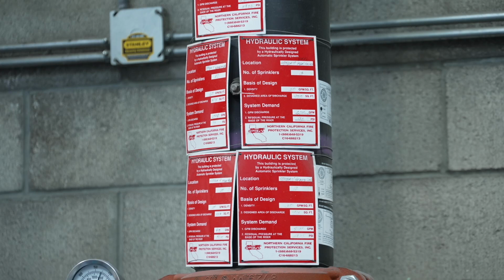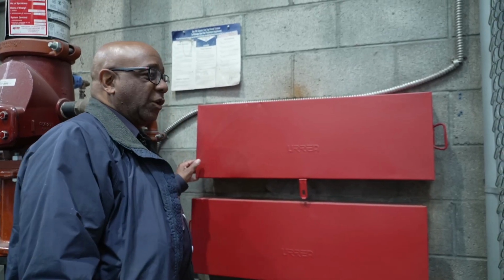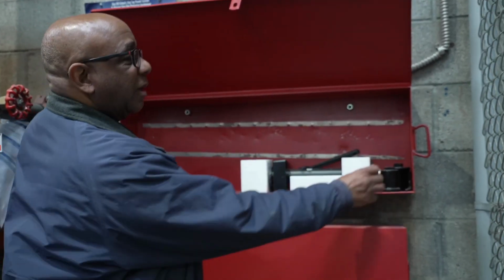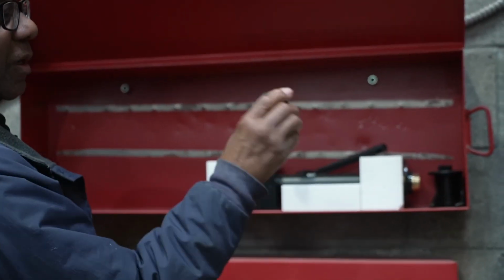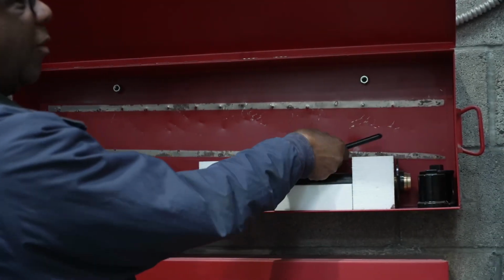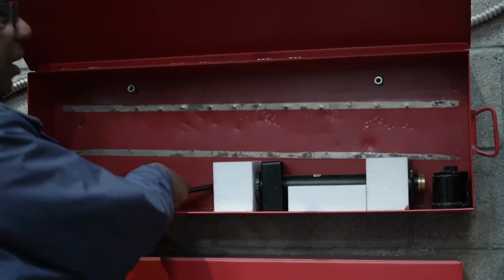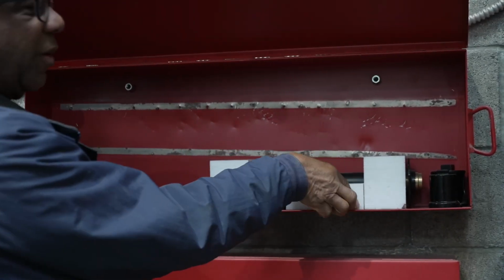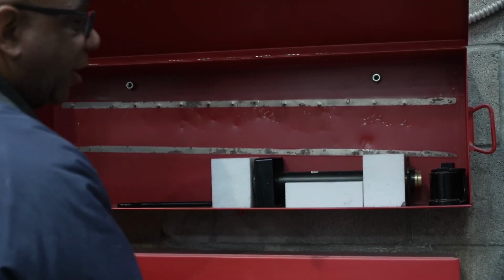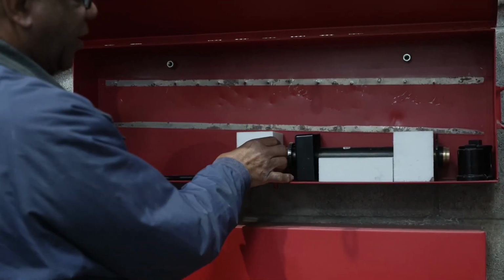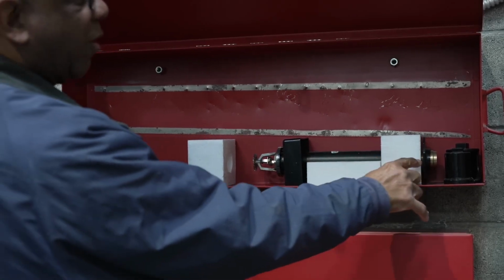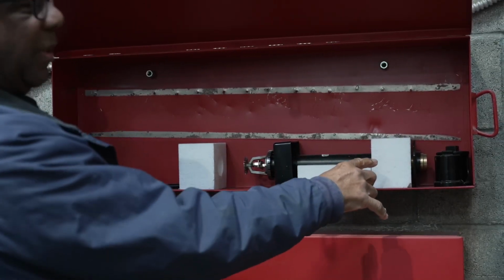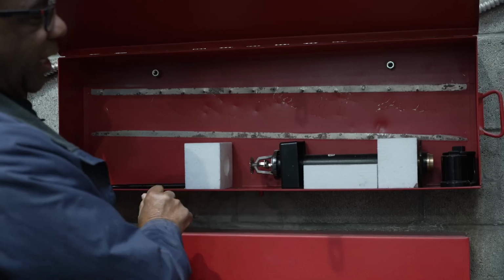So when you have refrigerated or freezer occupancies, there's going to be a specialty type of head. This box contains those. It has a specialized wrench, along with the standard wrench. These are a couple of hundred dollars each, so they're going to be in a box. In this particular case here, you can see the barrel of this dry pendant, and then you can see the sprinkler head that would be inside of it.